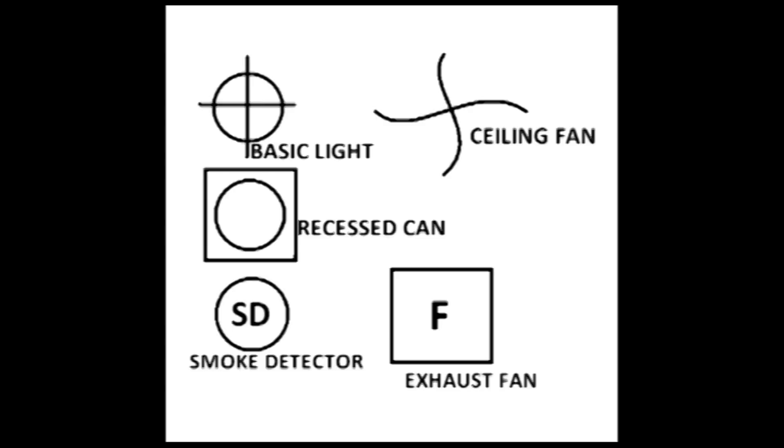The most basic is the light box, which is a circle with a cross through it. Followed by a recessed can, which is a circle with a square around it. We then have a smoke detector, which is SD with a circle around it. Followed by a ceiling fan, which is kind of a cheesy looking fan. And then we have an exhaust fan, which is a square with an F in it.